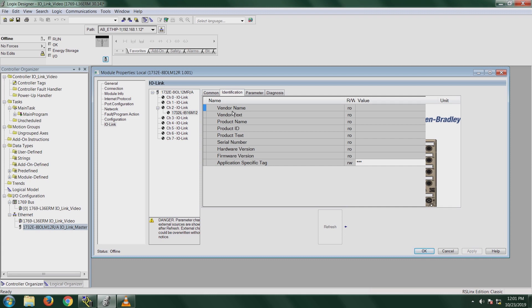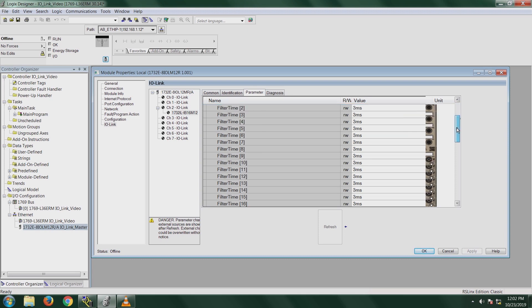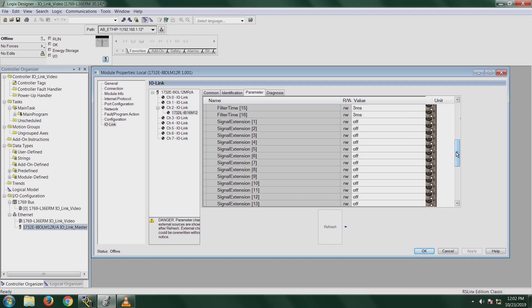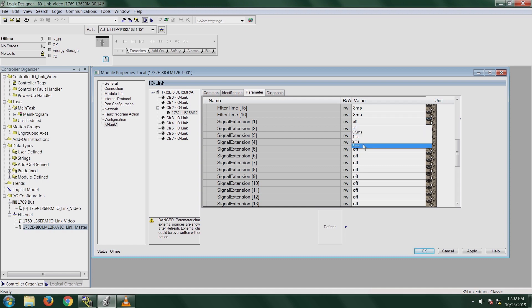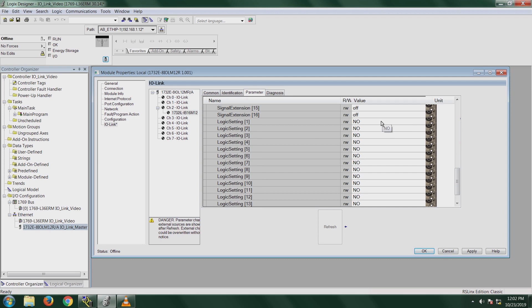The parameter tab is where you can actually configure different parameters within the IO-Link hub. The operation configuration will have your serial number and your electrical ID node tag and your module identification ID. Filter time specifies the filter time for each input. Your signal extension is the minimum time that the input stays in one value before switching to another value. This is a read/write, so you can change it anywhere from 0.5 milliseconds up to 3 milliseconds. Your logic setting, you can change whether your input is going to be normally open or normally closed. So you can actually invert a normally open sensor to normally closed based on your application specifications.